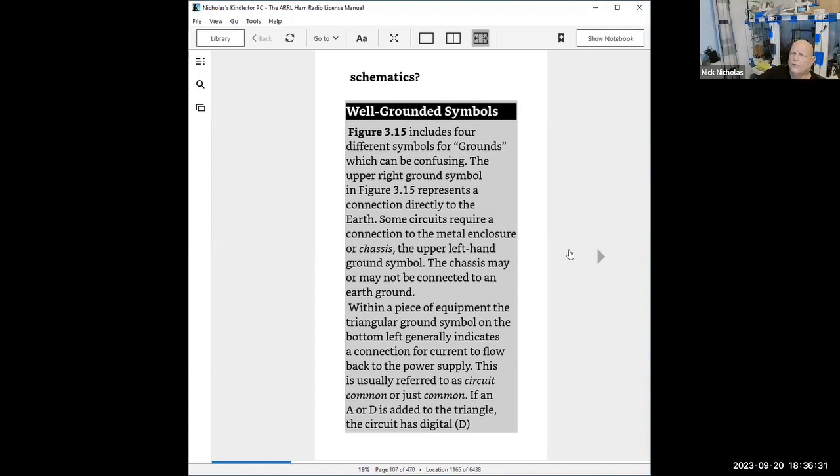And because hams are so confused about it, we've gotten a bit of folklore about grounding. About 20 years ago, the National Electric Code actually put a section in Article 810 to cover radio and electronic equipment, things like cable television installs, and it includes specifically ham radio and even CB stations. And fundamental, I think in 810.30 or 350, is a reference that you've got to adhere to NEC Article 250 on grounding and bonding.